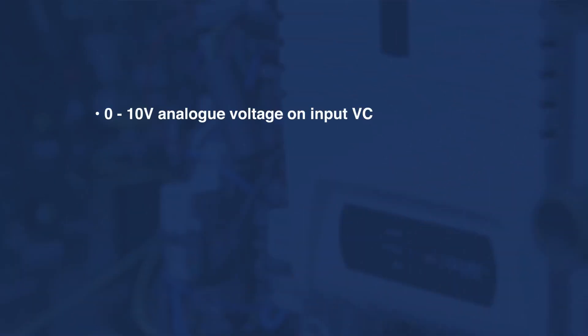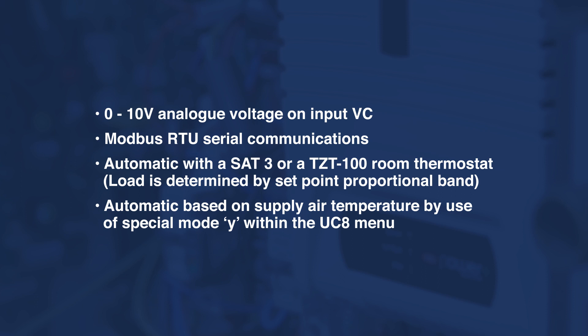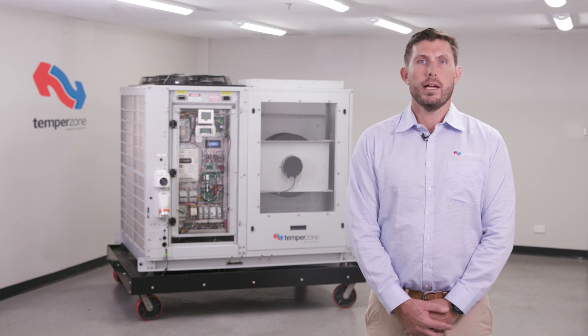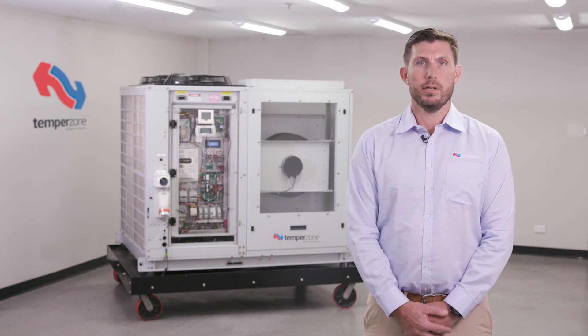Capacity input can be requested by four different methods: 0-10V analog control installed in the field to the VC terminal inputs on the UC8 controller; high-level BMS control by Modbus RTU serial communications terminated in the A1-B1 terminals of the UC8; temperzone controllers such as the TZT100 or SAT-3 will request capacity on a proportional band between set point and room temperature; or by supply air control within the UC8 controller by selection of special mode Y. Supply air control aims to maintain 12 degree cooling supply air temperature and 35 degree heating supply air temperature.